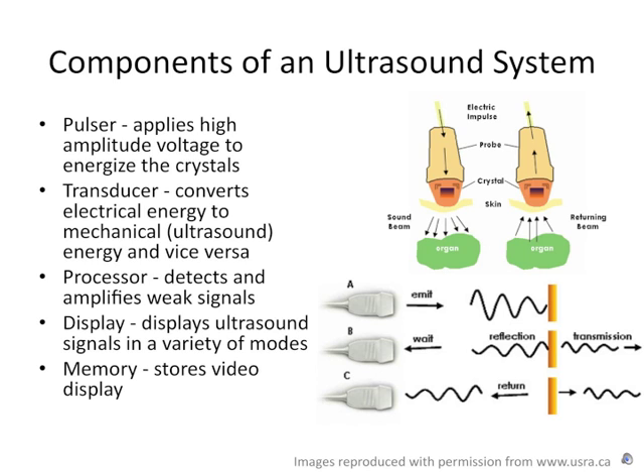An ultrasound machine requires a number of different components. A pulser applies high voltage in a cyclical fashion to crystals within the transducer array, causing the crystals to vibrate due to the reverse piezoelectric effect, generating ultrasound waves.